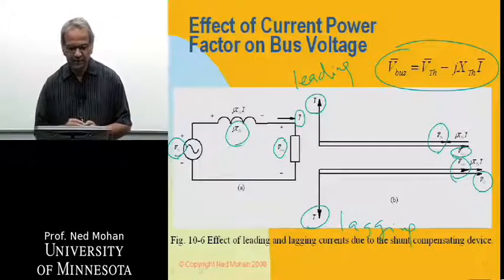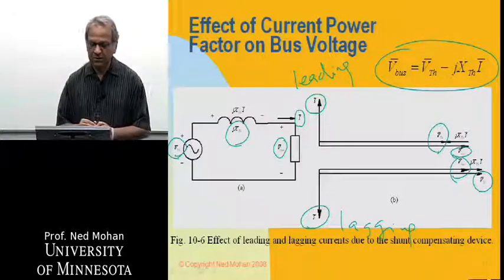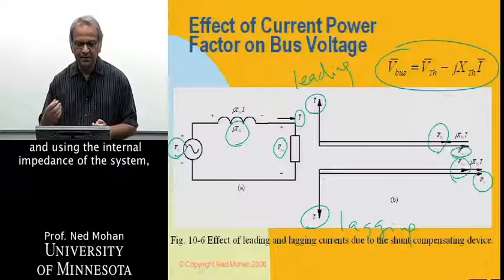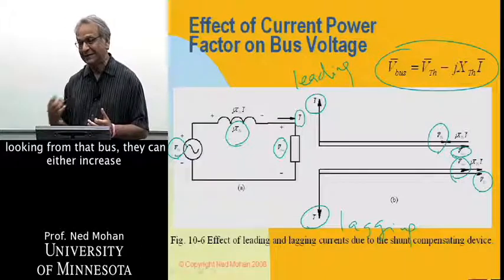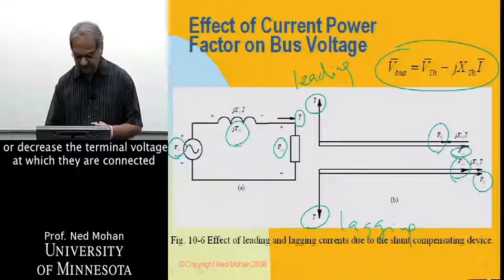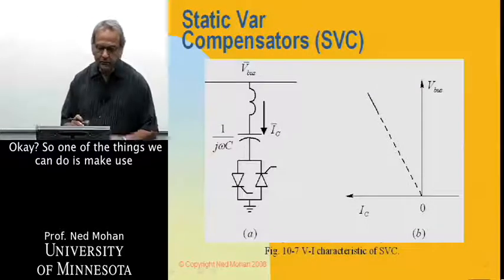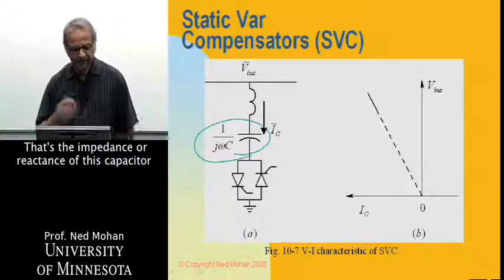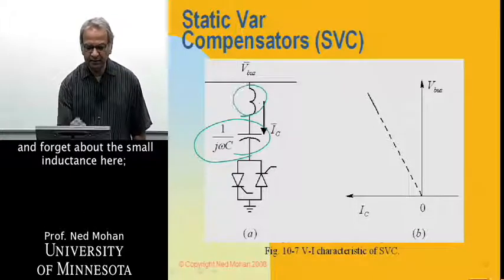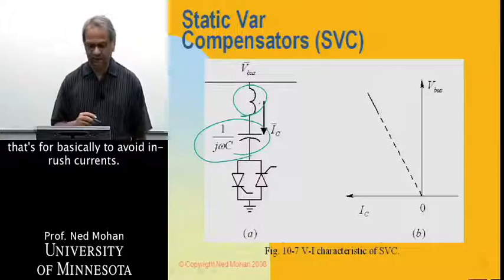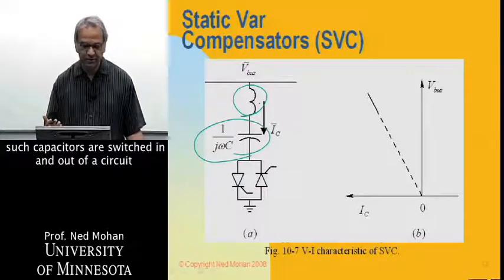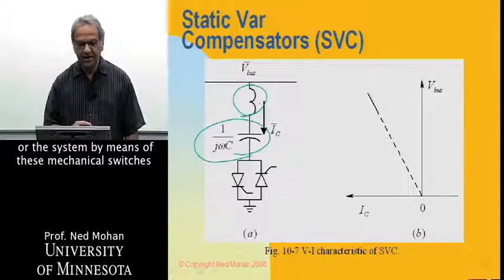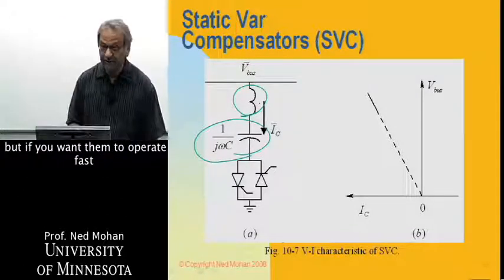That's the principle on which these static reactive power compensation devices work. They either draw a leading power factor current or a lagging power factor current, and using the internal impedance of the system looking from that bus, they can either increase or decrease the terminal voltage at which they are connected. One thing we can do is make use of capacitors — that's the reactance of the capacitor — with a small inductance to avoid inrush currents. We can use a mechanical switch to switch capacitors in and out of the system.